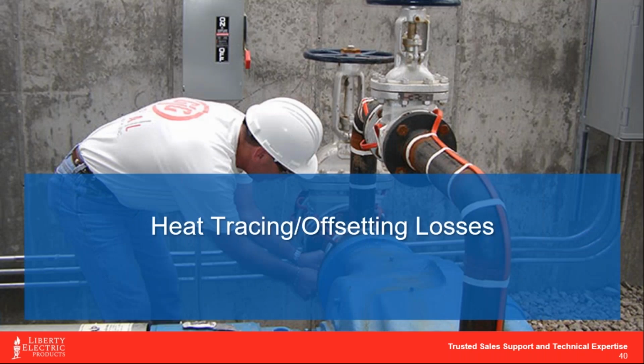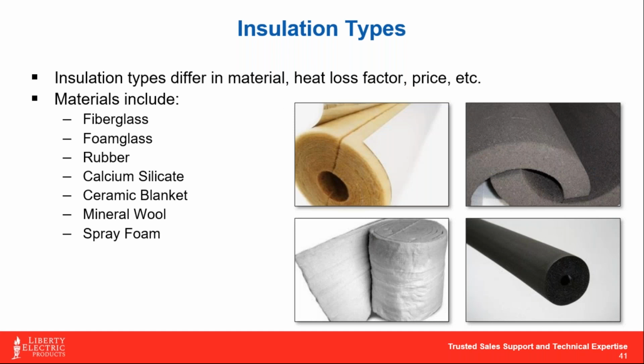Okay, so we're going to talk a little bit about heat tracing and offsetting the losses, because that goes hand in hand with tank heating. So insulation is your best friend for these types of applications, and quite frankly, it is an absolute requirement for your losses in most cases, okay? So a lot of different types of insulation out there.